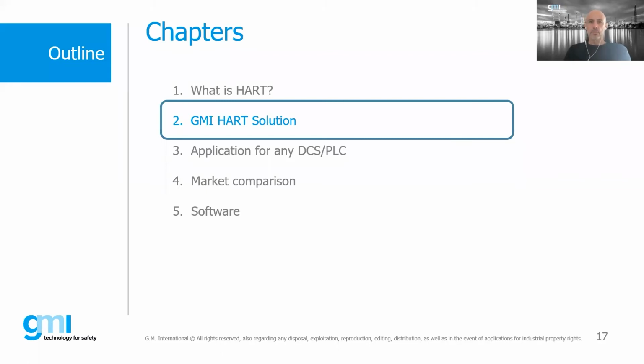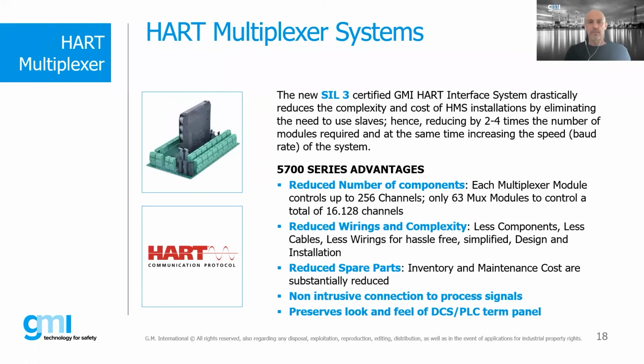What is the GMI HART solution? We have here the SIL 3 certified HART system multiplexer, which is a module connected to the termination boards. The main advantage is that you can use a single multiplexer for 256 channels. On the market, you basically find a multiplexer for 32 signals. So this reduces the cost for the application.